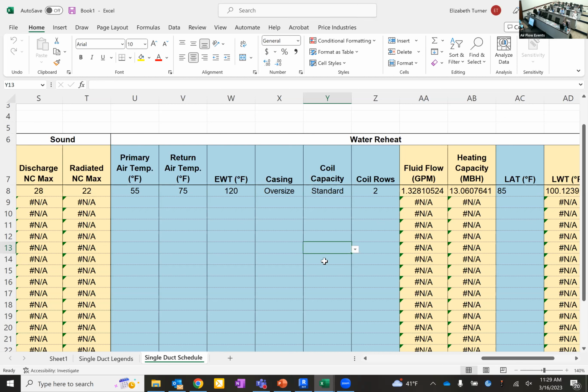Yeah, exactly. So I would also be checking leaving air temperature. You want to make sure of both capacity and leaving air temperature; usually you want to be meeting or slightly exceeding on both of those. So I'd be checking both, but then yes, I wouldn't always jump from 1-row to 2-row. I might check either a high capacity coil or keep it at 1-row but go oversized casing. You have 3 or 4 different options to play with and look at. Maybe 2-row oversized gets you even closer, I don't know. But jumping rows shouldn't just be the automatic, I'm always gonna increase a row.